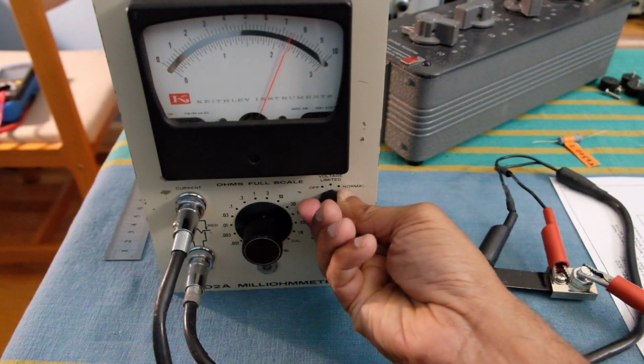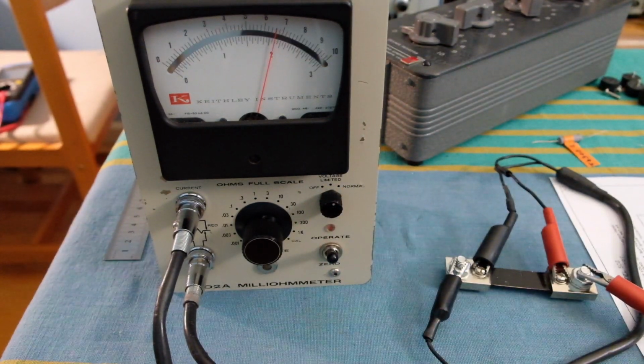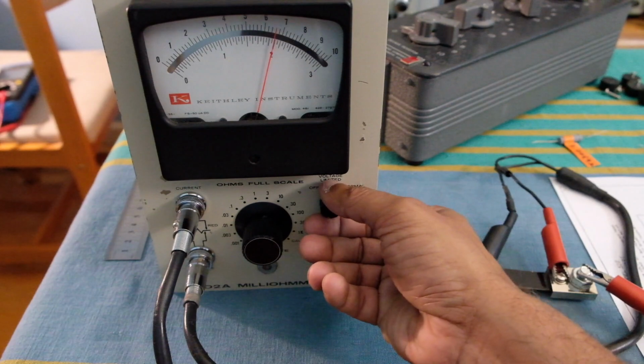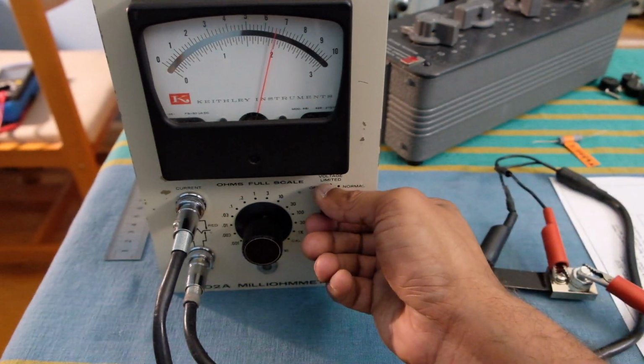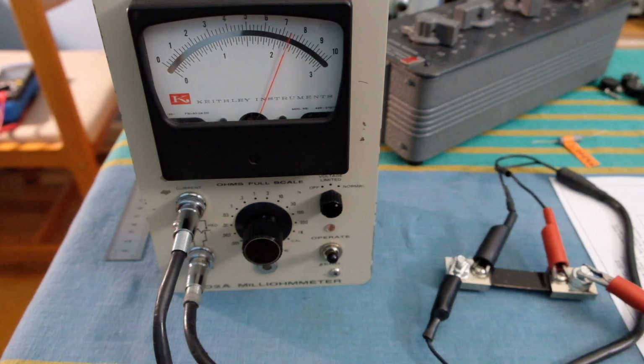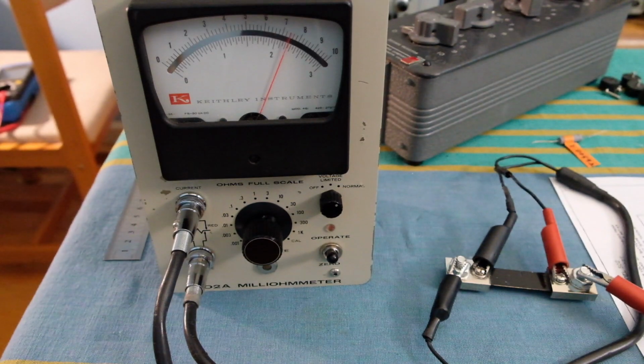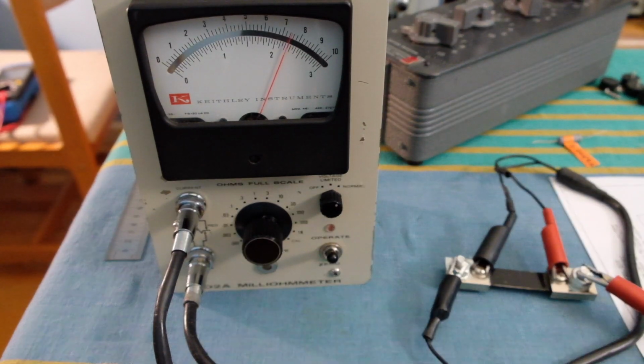If I go to this other range, you'll see it drops off quite a bit. I mean, you need a lot more current actually to send into this one. I think the amplifier doesn't have enough sensitivity on that, or may need calibration. But if I go back to the normal operation, it puts a larger current into this thing, and it's got enough gain to show that accurately. So this is the ultimate test for me in terms of measuring tiny resistance below 1 milliohm, and this instrument will do that. So will the other HP, and I've done similar measurements with that, but I haven't compared it head to head with this particular instrument.